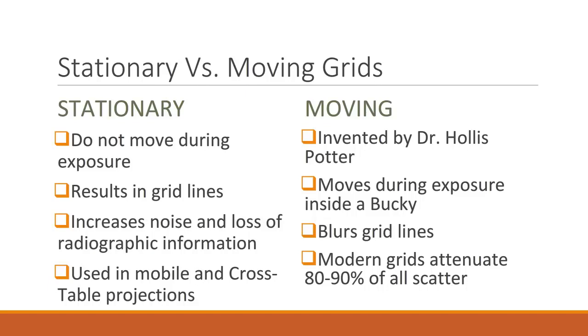To reduce the visualization of grid lines, Dr. Hollis Potter invented a moving grid that actually moved during the exposure. When the rotor button is engaged, the grid inside the table or upright Bucky begins to move continuously, but only a small amount of movement back and forth. Because of this movement, the lines are blurred but the scatter radiation is still blocked by the lead strips.